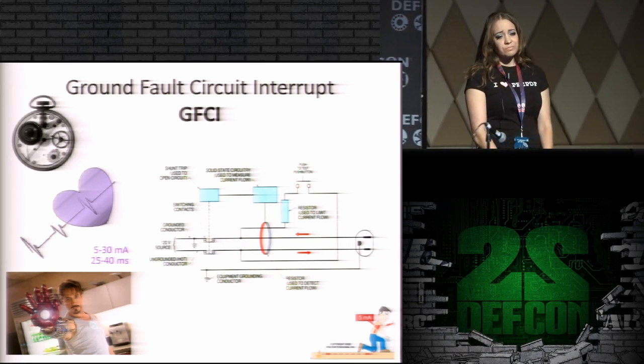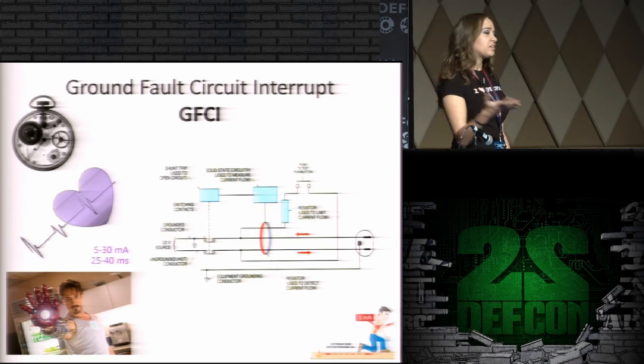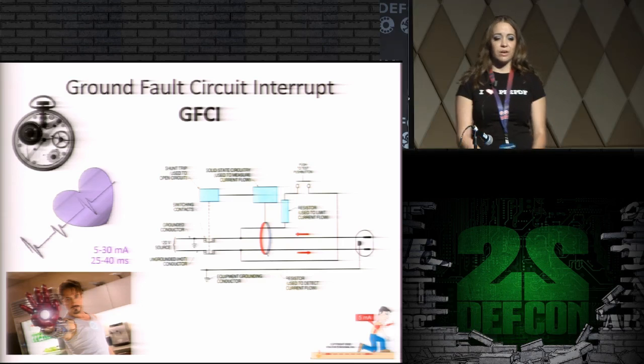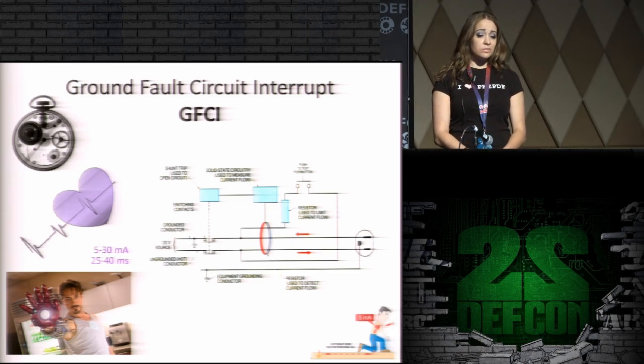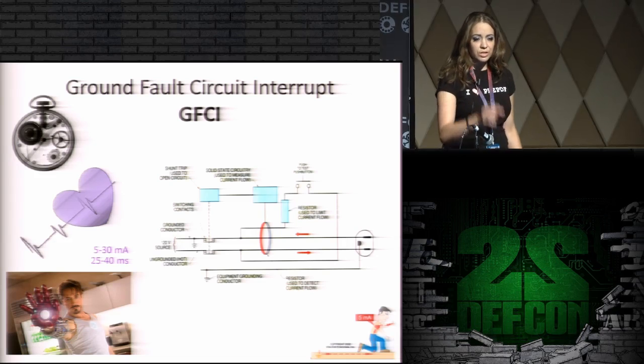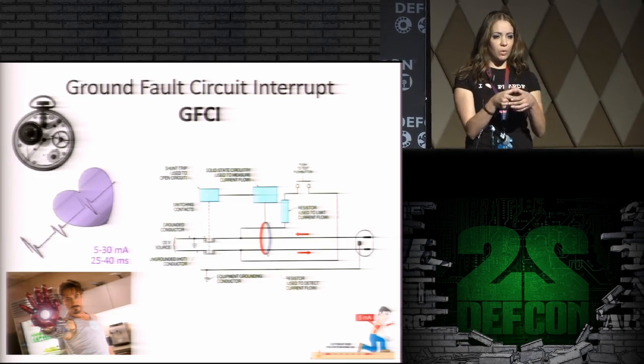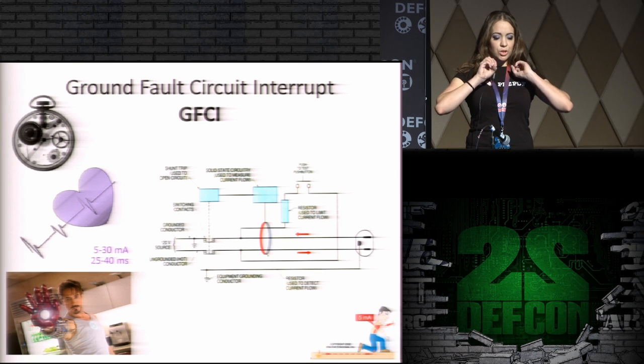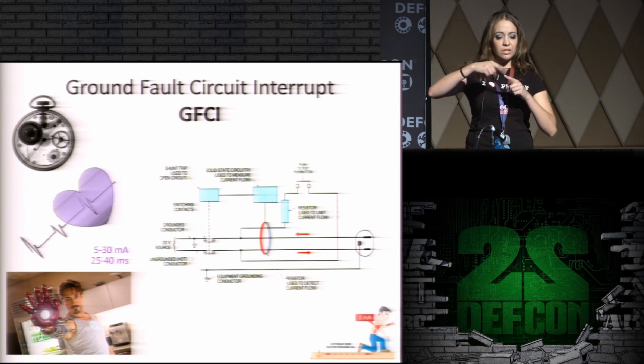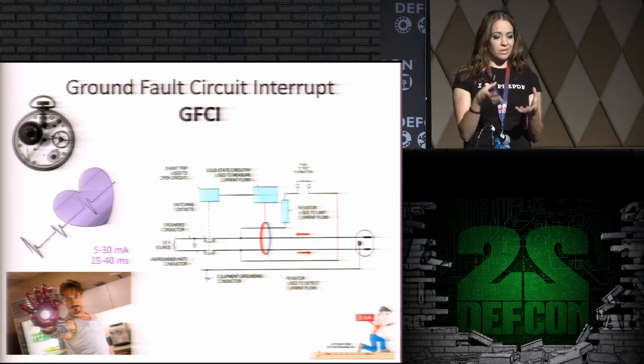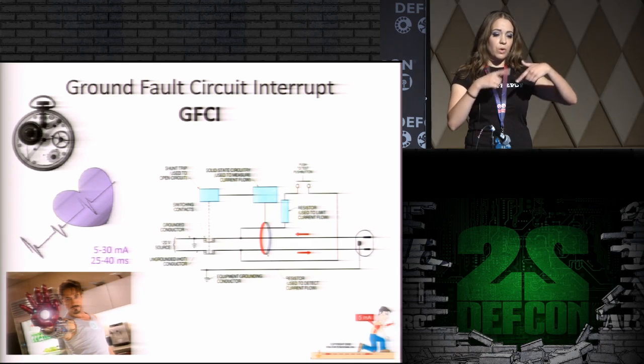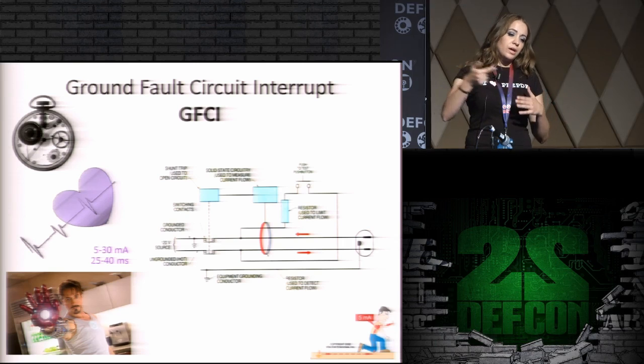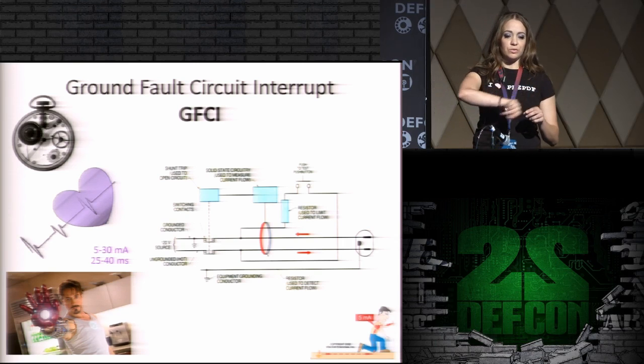So this is how GFCIs work, their little diagram. It's really quite simple. It's a little transformer with a magnetic core, a toroid. There's an insulated copper wire that goes around it, like a general normal transformer. Through it go the wires - the hot wire on the way out and the neutral, or the hot wire on the way in and the neutral on the way out.